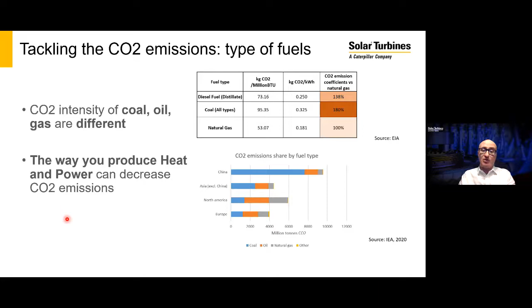If the plant is using the grid, the grid itself will need some fuel to produce electricity. For a combined cycle, you would need 11.5 megawatt to produce this 5 megawatt of electricity. For the steam, considering a boiler, for this 8 megawatt you need 10 megawatt of fuel, for a total of 21.5. Comparing to a combined power in this case with gas turbine, 5 megawatt natural gas fired, you would need only 17 megawatts.